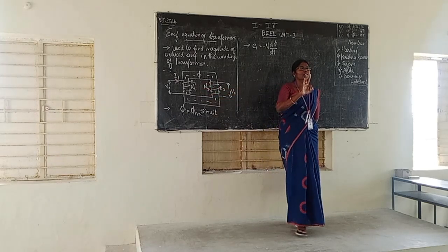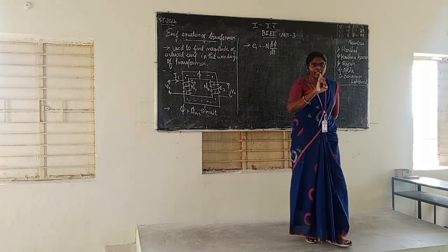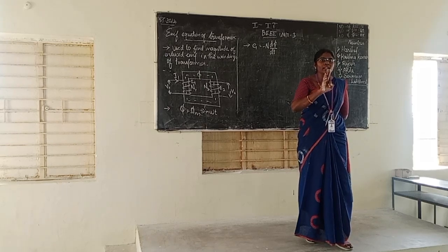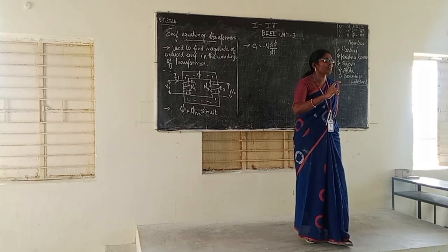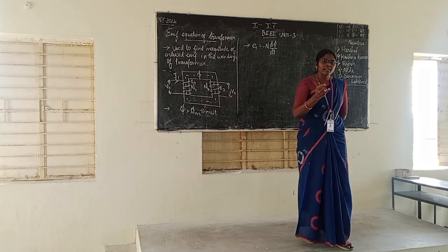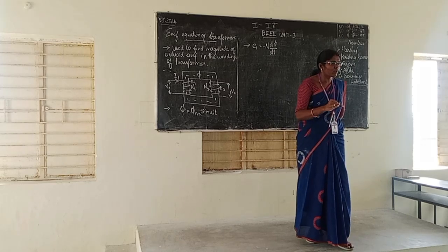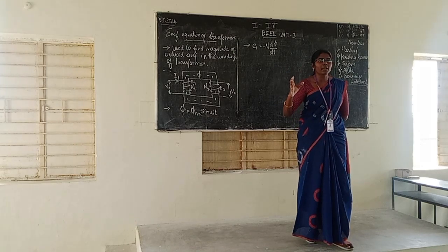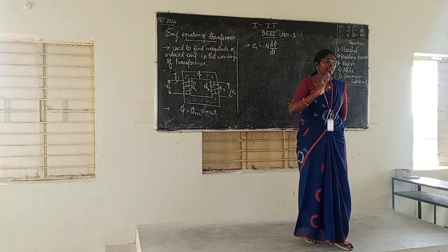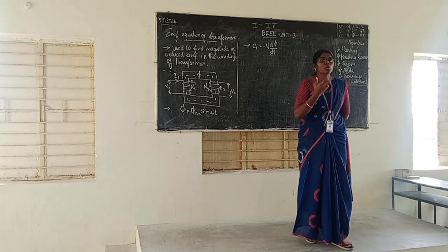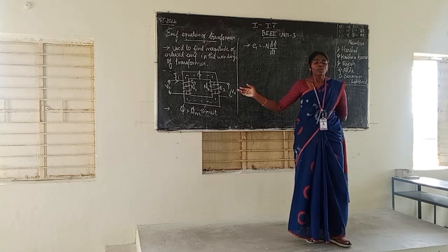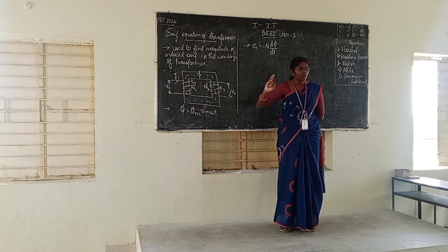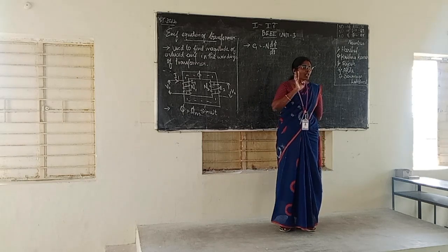Okay, there are three things in the construction of a transformer. One is the windings. Next is the magnetic core. The other one is isolation. If it is a small size transformer, isolation is made by air, a simple air, or vacuum or gas. If it is a large size transformer, the isolation is done by mineral oil. That can also serve a role for cooling purposes. So these are the three things in the construction of a transformer: magnetic core, windings, as well as isolation.